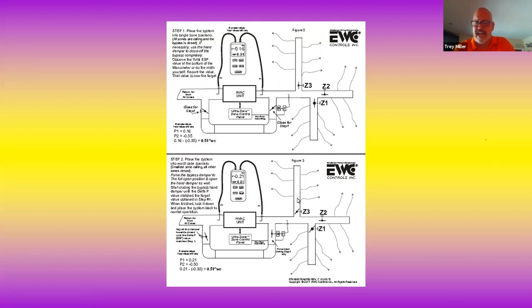Now to balance it out, I have to go down, open up the bypass, and shut the smallest zones. The only zone that we want to call is the smallest zone, shut the other zones. Now we're going to cut the system on with the bypass open, go to the hand damper, and slowly turn the hand damper to where we can meet the static pressure. Now our system is balanced.